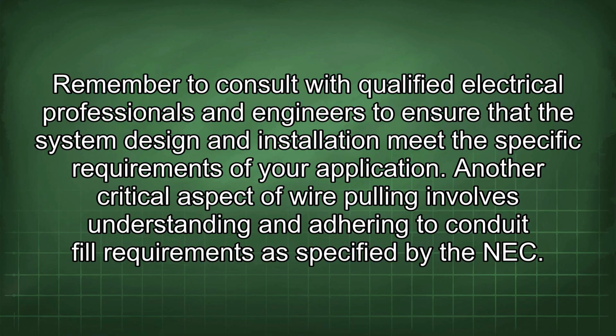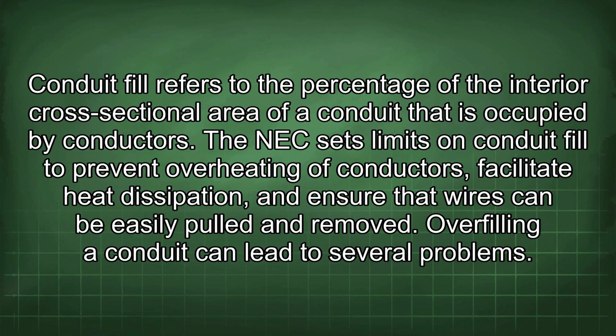Another critical aspect of wire pulling involves understanding and adhering to conduit fill requirements as specified by the NEC. Conduit fill refers to the percentage of the interior cross-sectional area of a conduit that is occupied by conductors. The NEC sets limits on conduit fill to prevent overheating of conductors, facilitate heat dissipation, and ensure that wires can be easily pulled and removed.